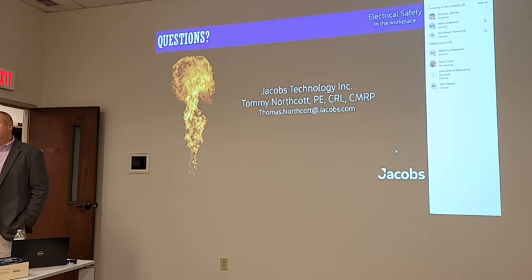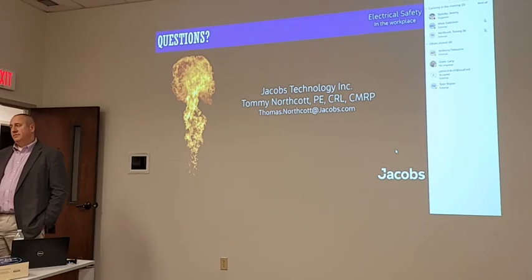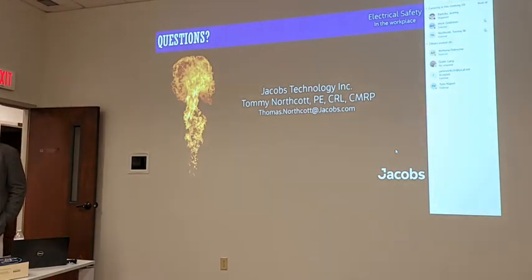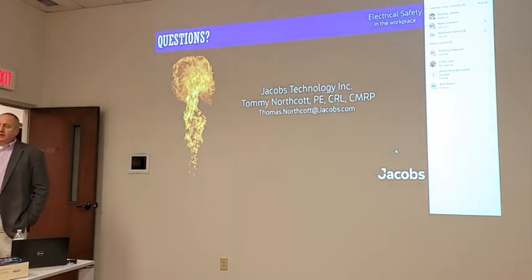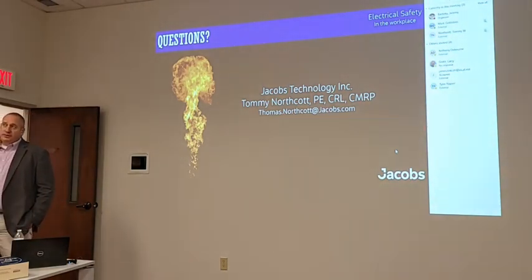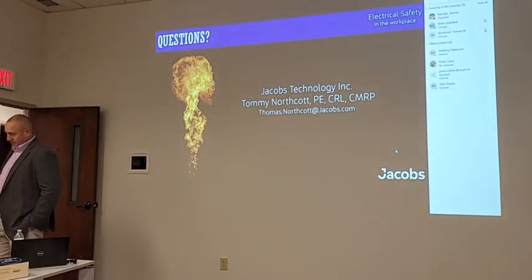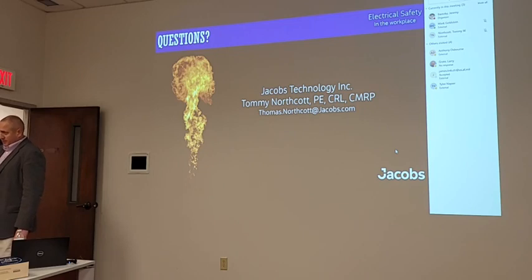Because you've got a breaker inside that panel in front of that starter. Most of the time you see the sticker on the panel, it's going to be for what's on the line side of that breaker. But does it apply to the motor starter inside that panel? There are 2 different scenarios there. If you've got a single enclosure, like just a panel, then it's going to be the main breaker, because a fault down here is most likely going to propagate into a fault on the line side of that main breaker, because it's all one open enclosure. And so in that scenario, you go by the main breaker incident energy level.